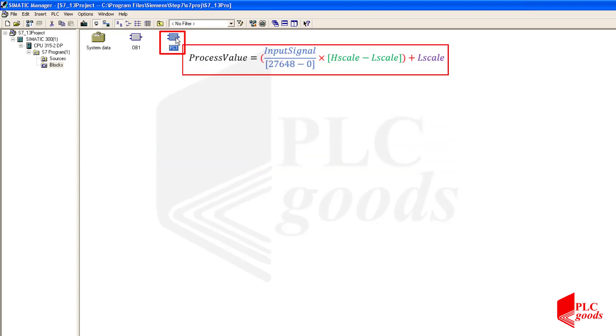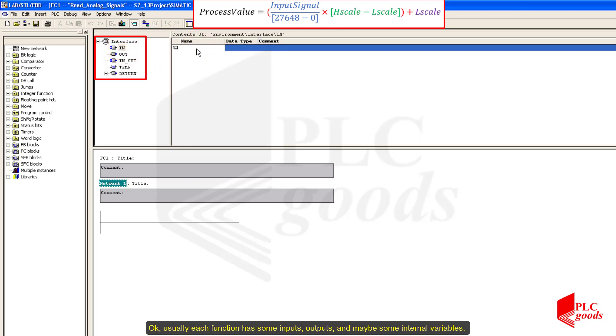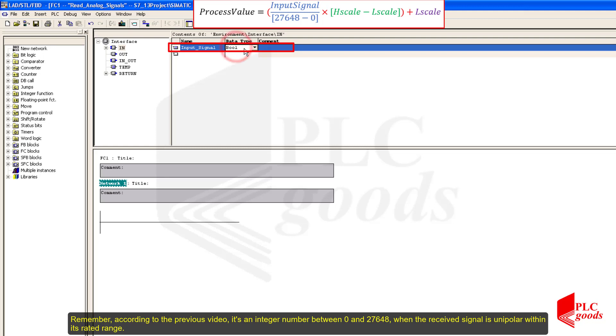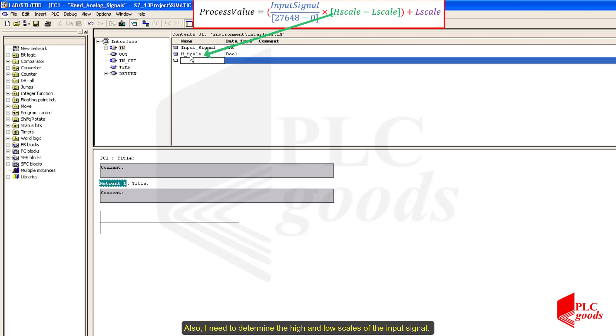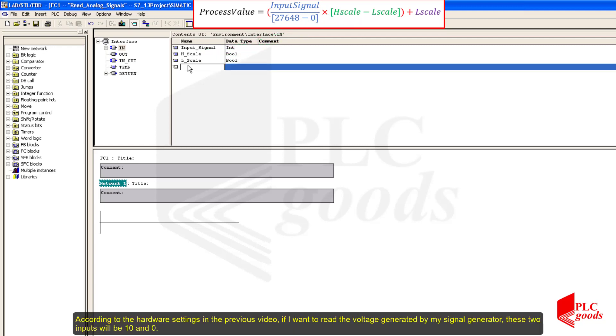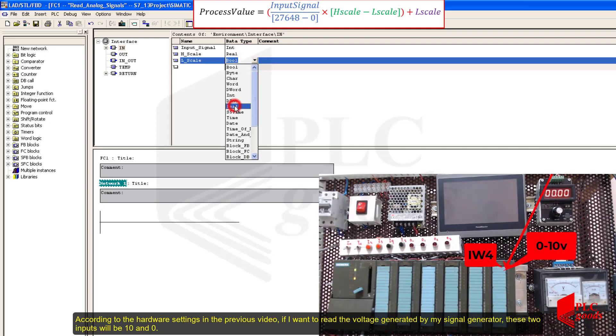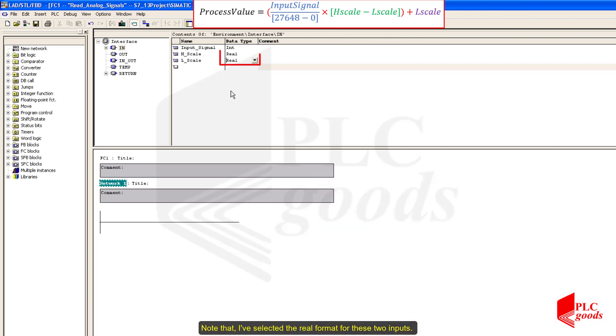Usually each function has some inputs, outputs, and maybe some internal variables. I need three inputs. The first one is the received analog input signal. According to the previous video, if I want to read the voltage generated by my signal generator, it's an integer number between 0 and 27648 when the received signal is unipolar within its rated range. I also need to determine the high and low scales of the input signal. I've selected the real format for these two inputs.